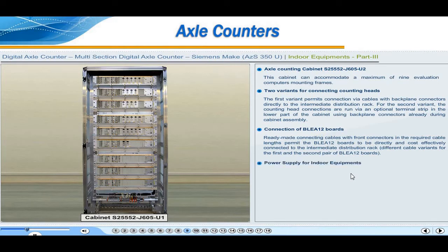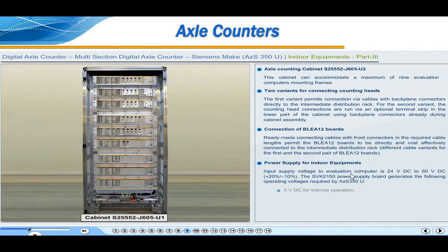Power supply for indoor equipment. Input supply voltage to the evaluation computer is 24 volt DC to 60 volt DC with tolerance plus 20% and minus 10%. The SVK2150 power supply board generates the following operating voltages required by AZS350U: 5 volt DC for internal operation, and 70 volt DC for external operation of maximum 5 counting heads.